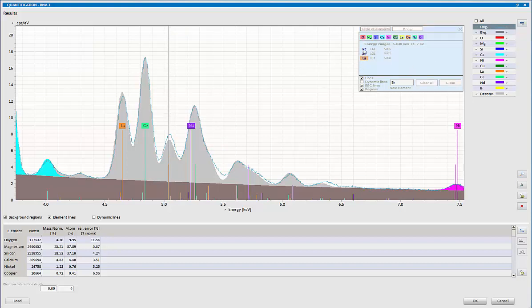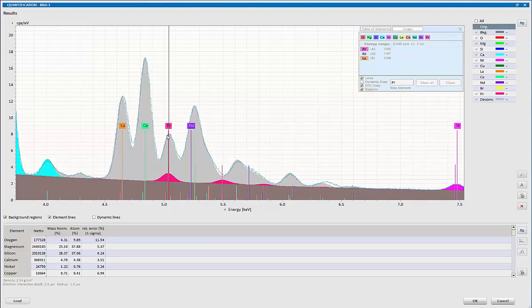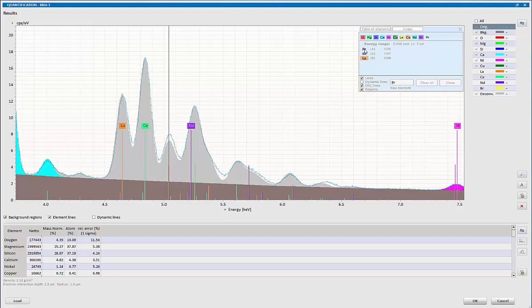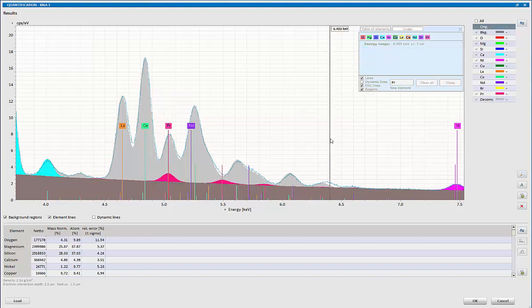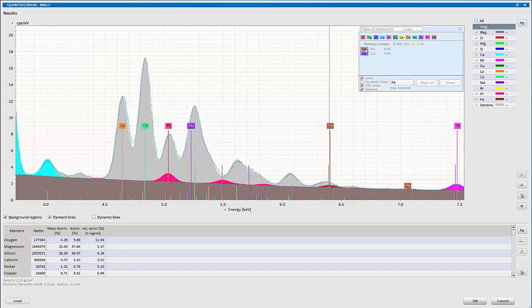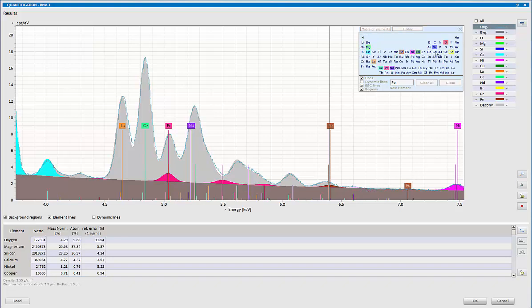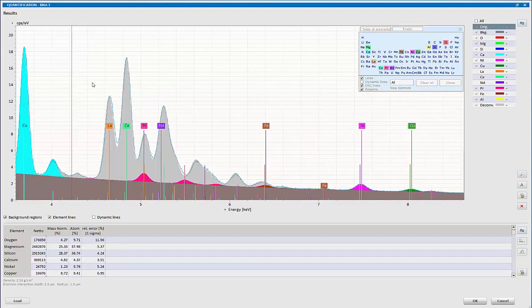So pointing to that and double clicking brings back the periodic table. Now when I click on Praseodymium, it immediately filled that area in and shows me the results of it. If I take it out, we can immediately see what the effect is. So obviously, we missed a little trace of Praseodymium. We can do the same thing over here. And we see iron as a possibility. And again, as soon as I click that in, it fills it out. So we can go through the analysis list, make any adjustments that we wish for any element, and have the system updated for me automatically.